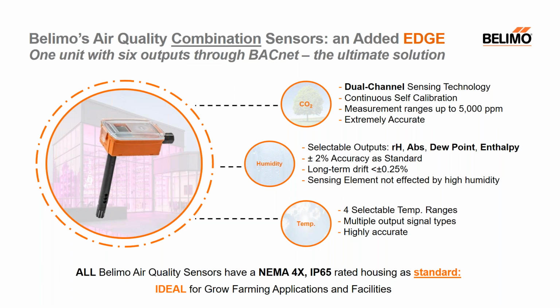On the humidity side, we've incorporated the same features as our standalone humidity sensor as well, which will include field selectable humidity outputs with relative humidity, absolute humidity, enthalpy, and dew point, also carrying over its 2% accuracy. On the temperature side of things, we were also able to incorporate the 4 selectable temperature ranges as well as multiple types of output signals in an attempt to be as easily integrated as possible.